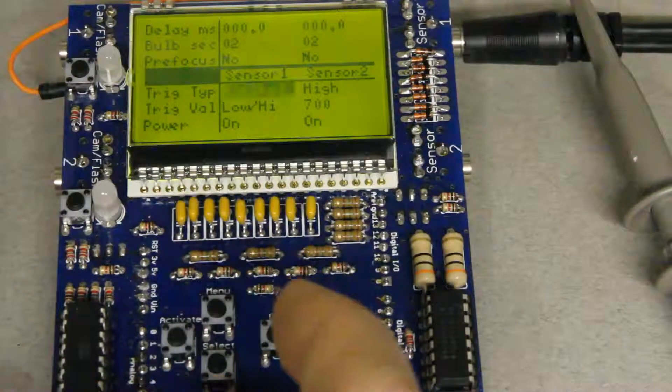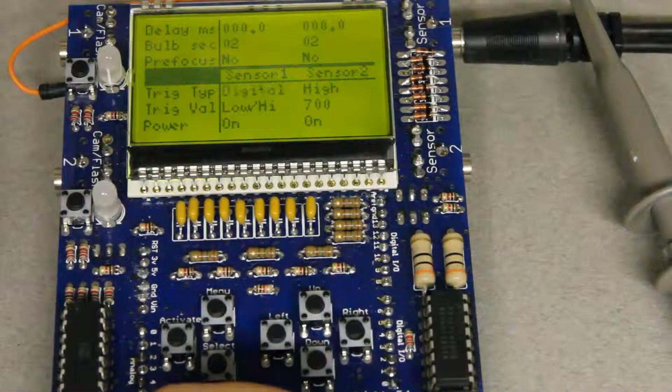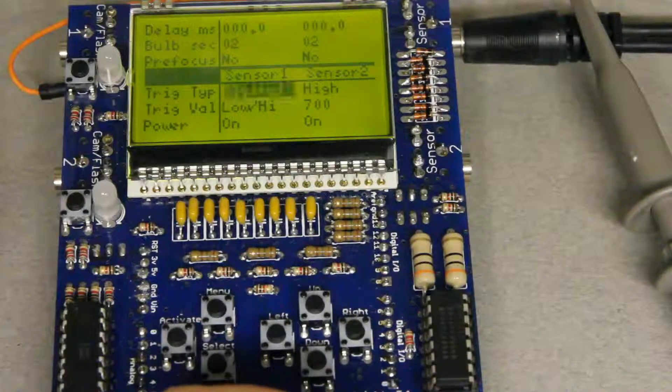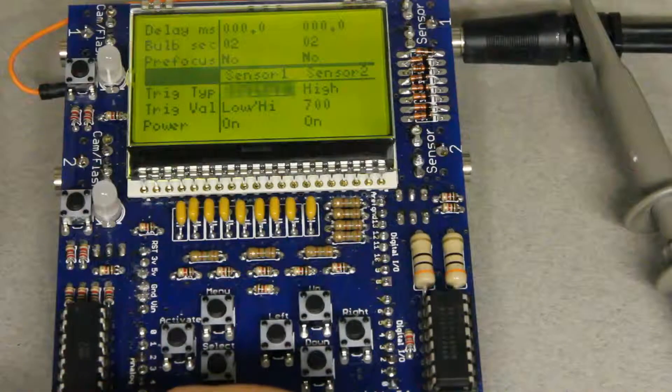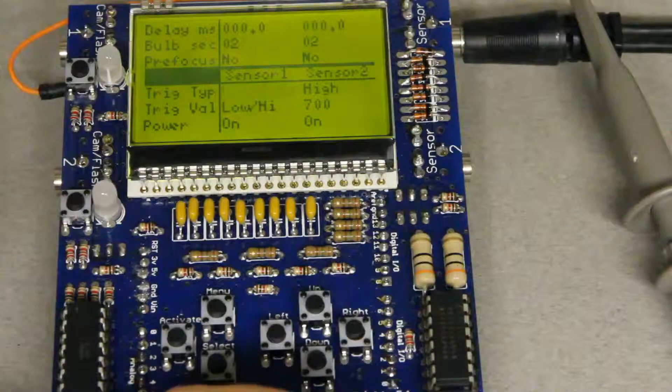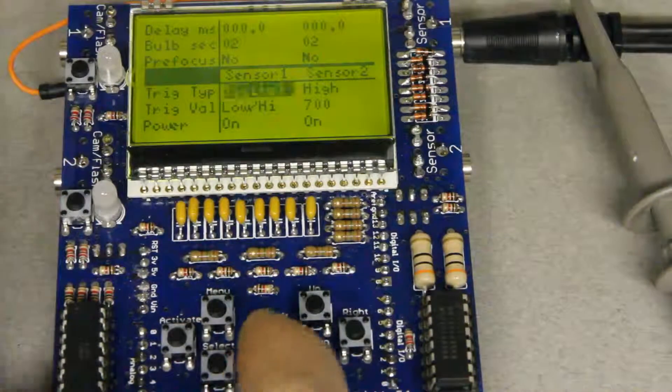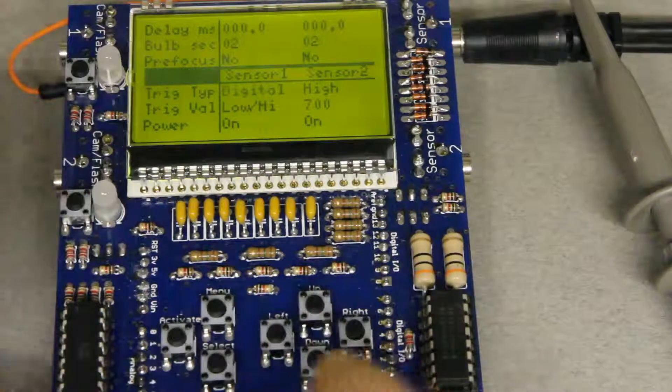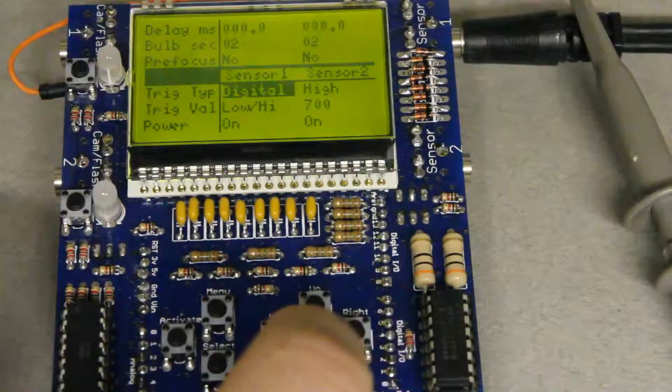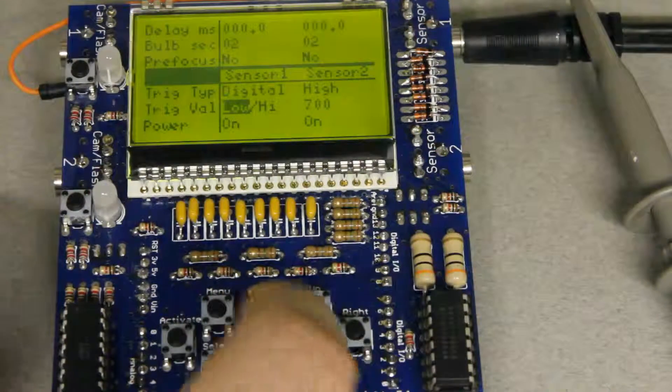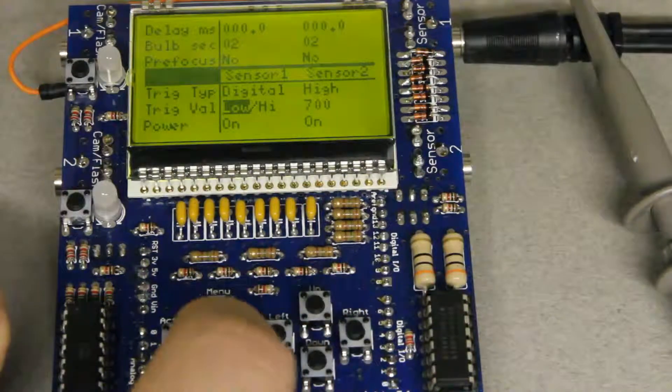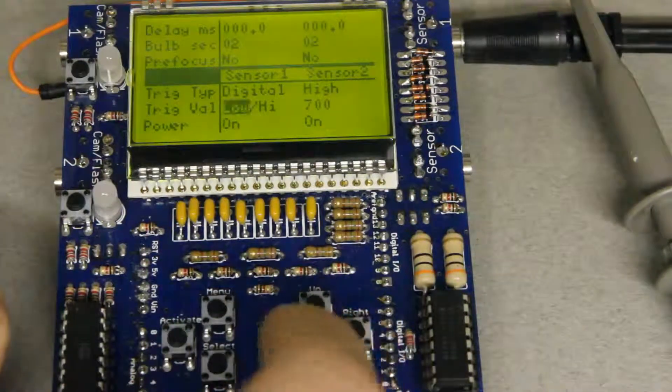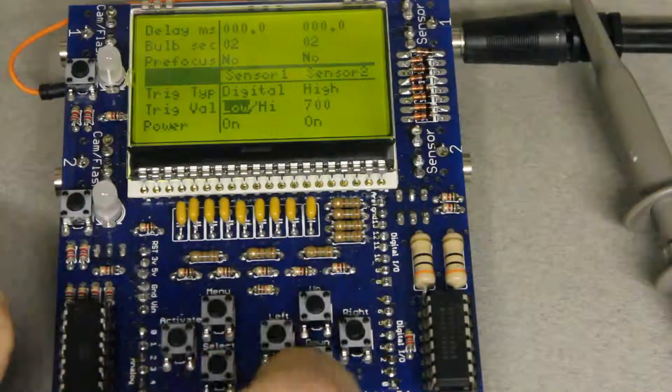It takes about 100 microseconds to read an analog signal and about one microsecond to read a digital signal. So that's about 100 times faster for digital signals. So when I've selected digital for the type and I go over here to value I can either select low or high, those are the only two options.